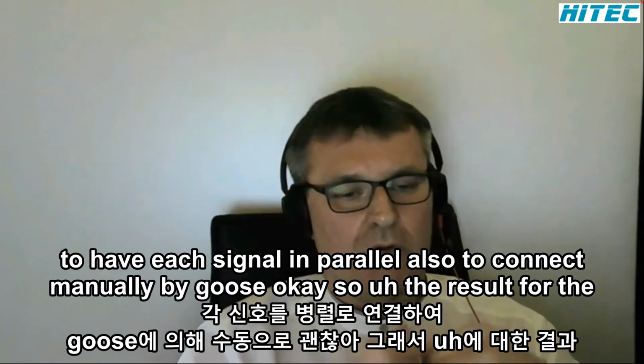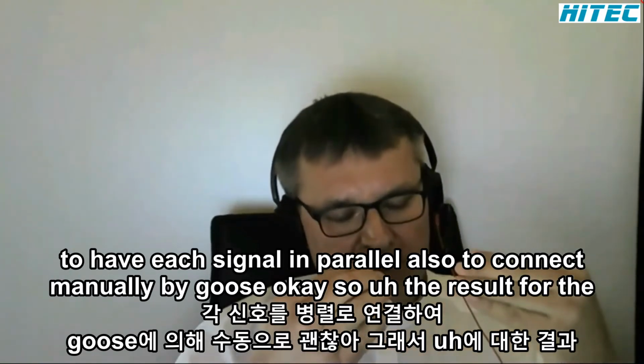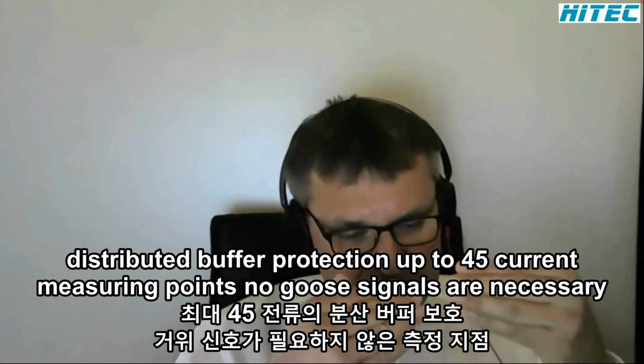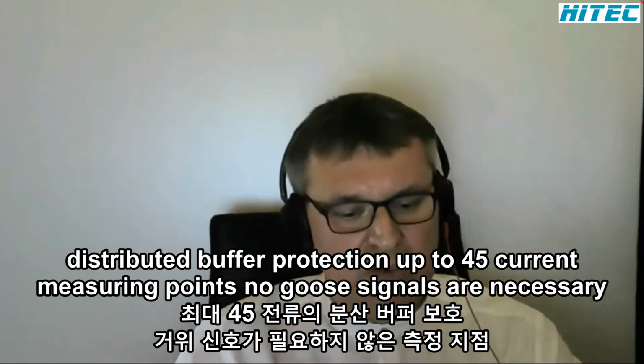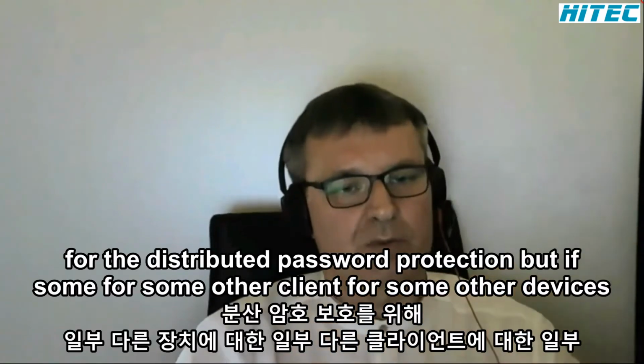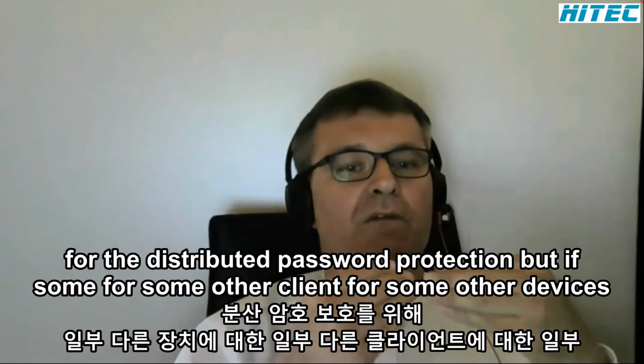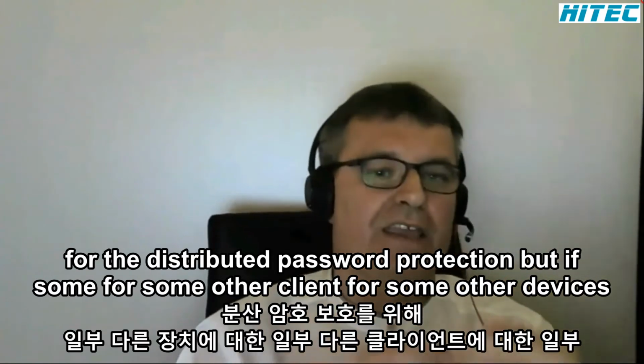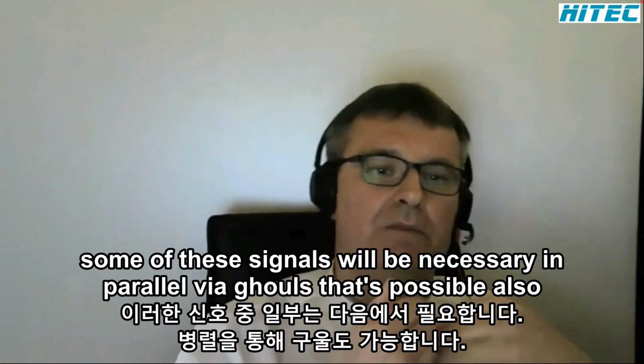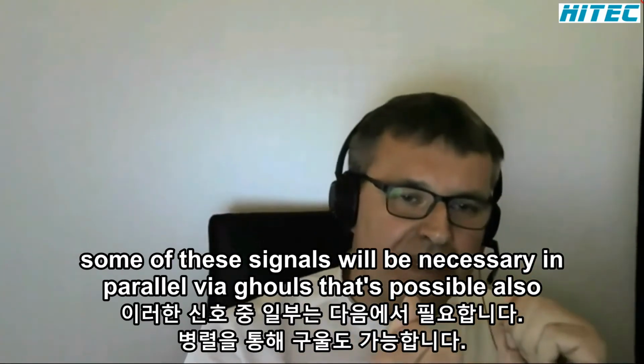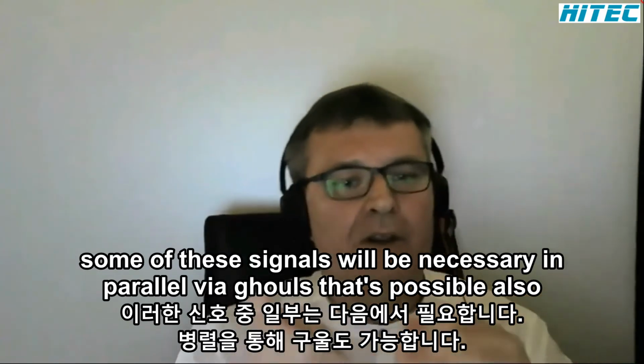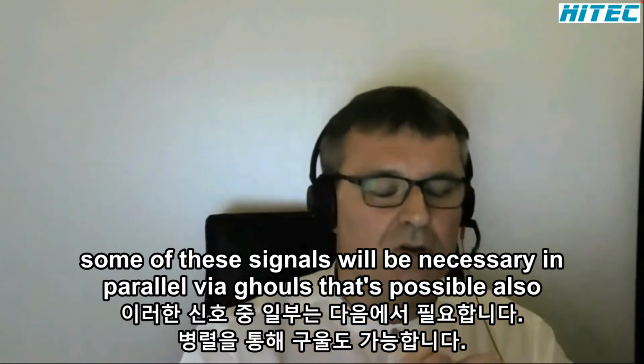Okay. So the result for the distributed busbar protection up to 45 current measuring points, no GOOSE signals are necessary for the distributed busbar protection. But if for some other clients, for some other devices, some of the signals will be necessary in parallel via GOOS, that's possible also.